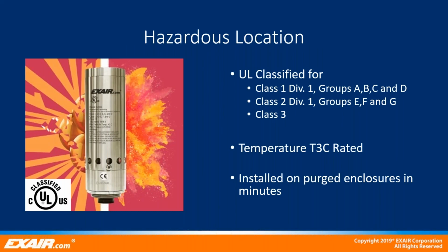EXAIR's hazardous location cabinet coolers are engineered for use with purged electrical enclosures. The HazLoc cabinet coolers are not purged and pressurized control systems and should not be used in place of a purged and pressurized controller. They are meant for use in conjunction with a purged and pressurized control system. These systems have been approved and tested by UL for use in the following areas. Class 1 Div 1, groups A, B, C, and D. Class 1 typically refers to the presence of a flammable gas or vapors in quantities sufficient to produce an explosion or ignitable mixtures.